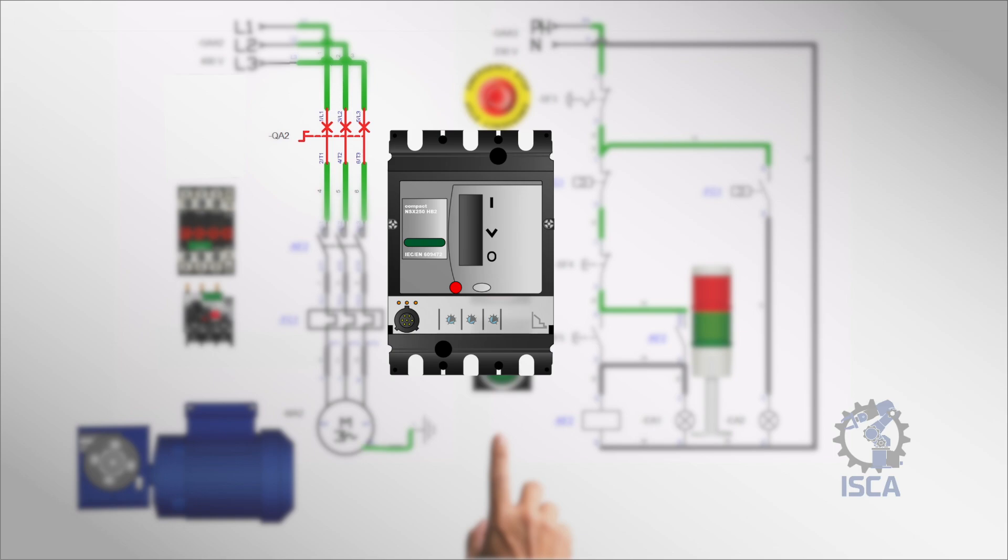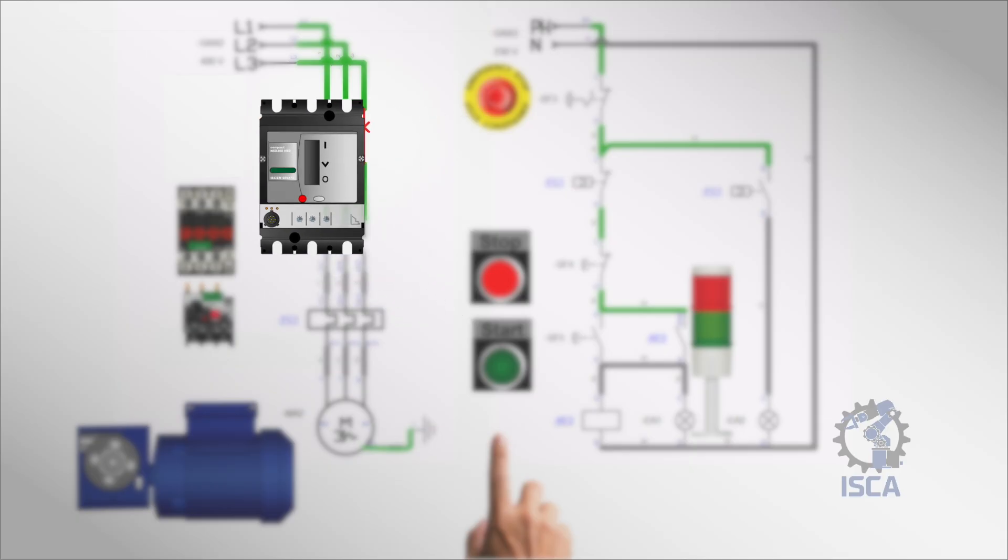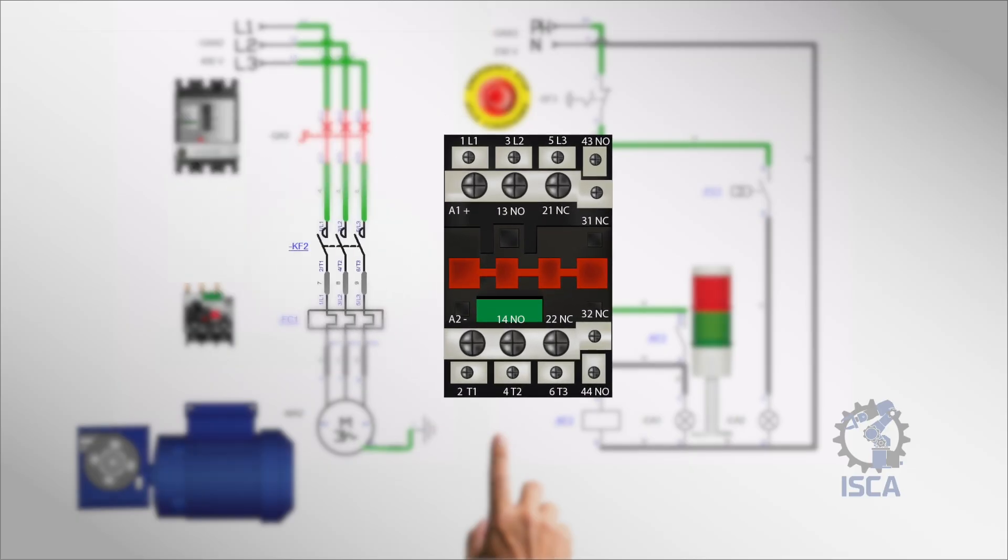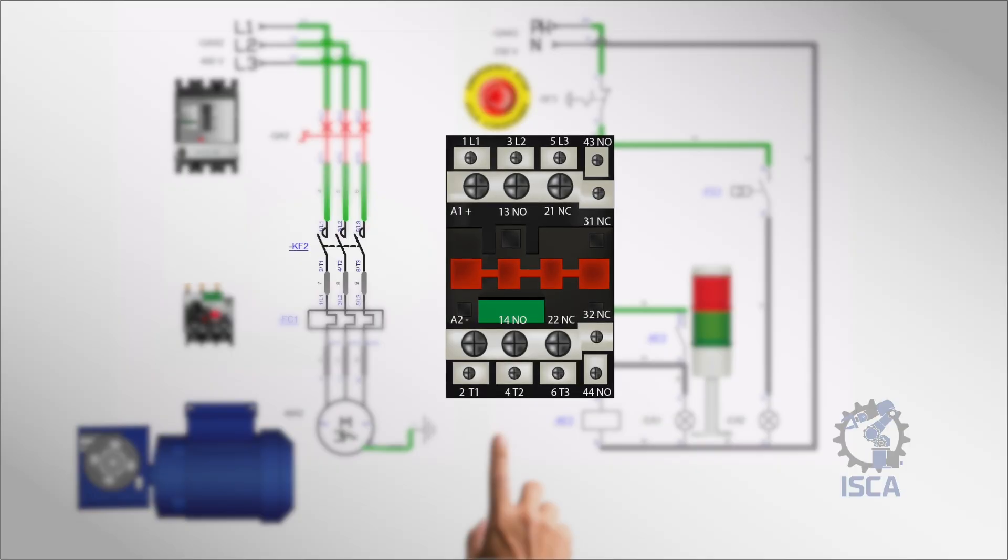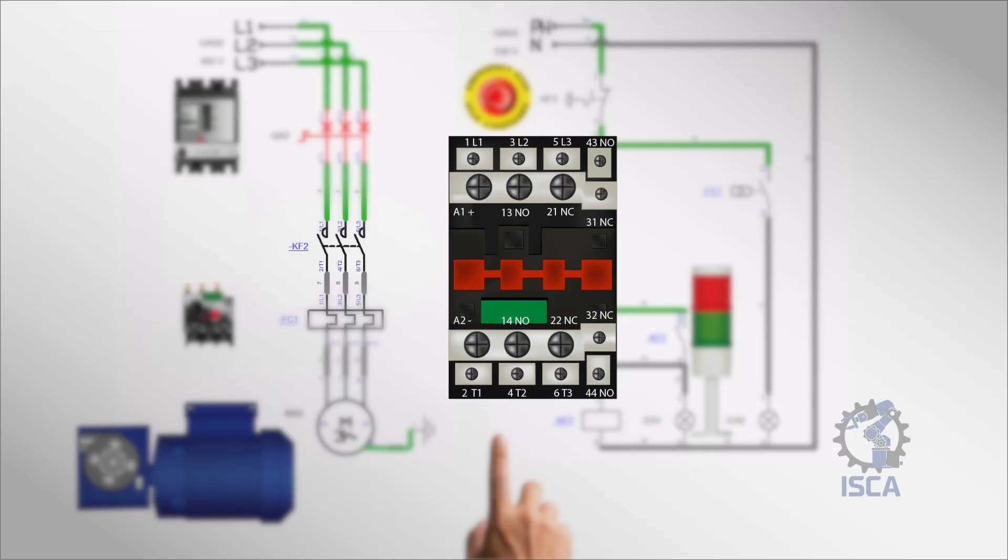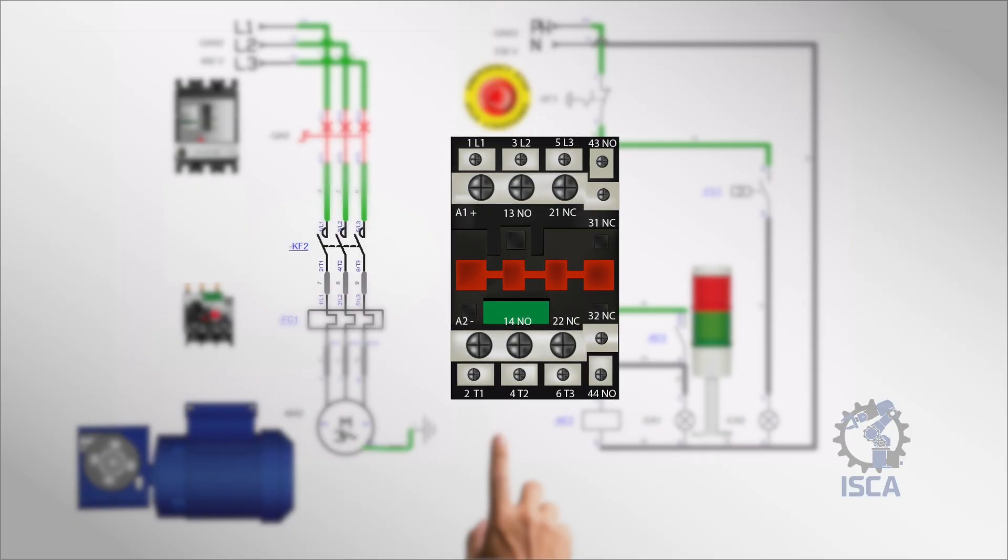Magnetic contactor: this is an electrically operated switch used for controlling power circuits. When activated, it uses an electromagnet to close or open the main power contacts. In a DOL starter, the magnetic contactor is responsible for connecting and disconnecting the motor from the power supply. It can handle frequent switching of high current loads, making it ideal for motor control applications.